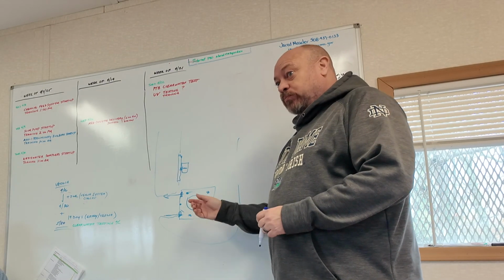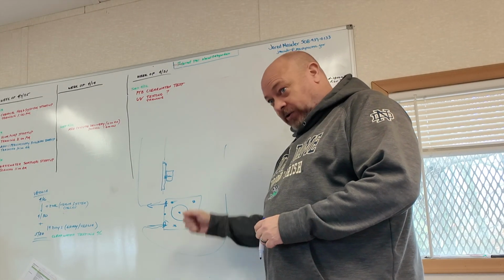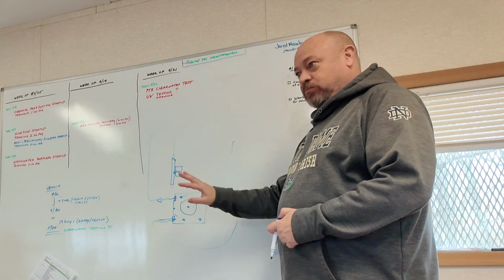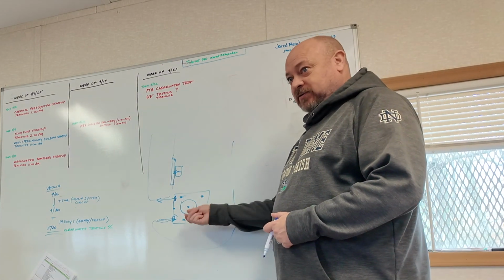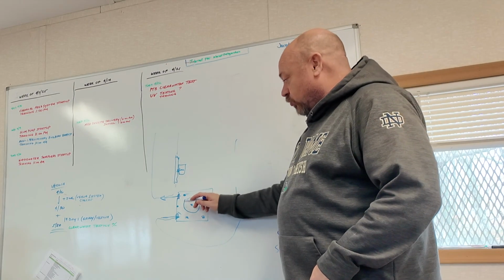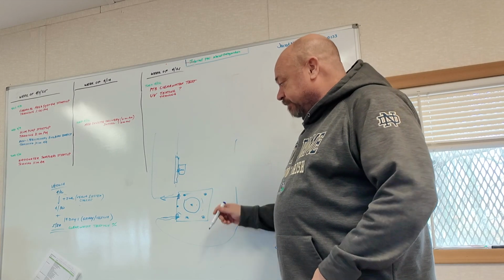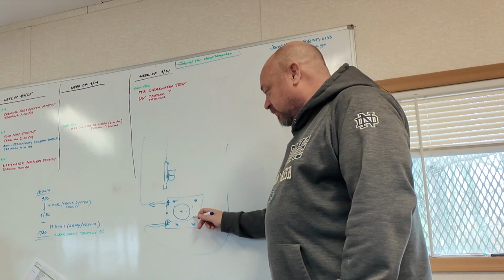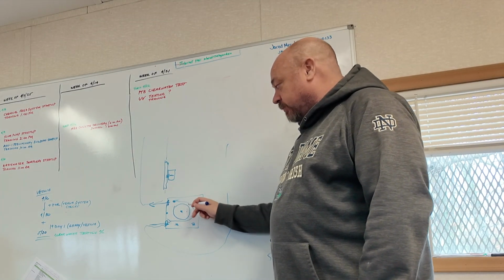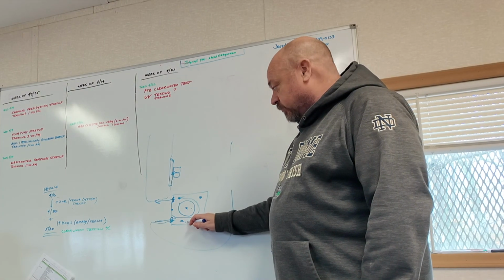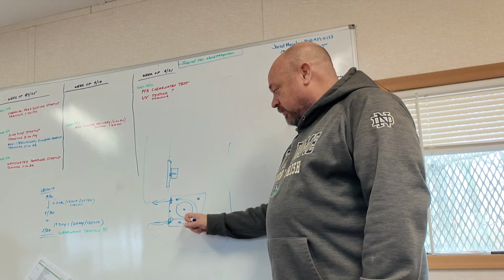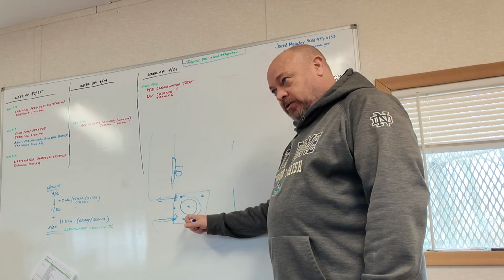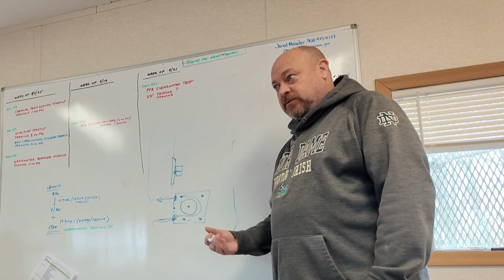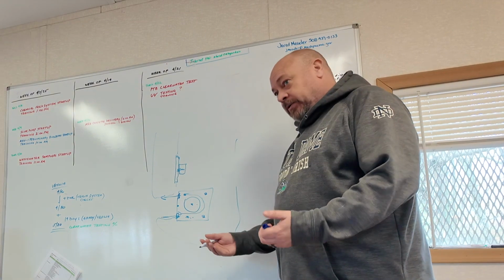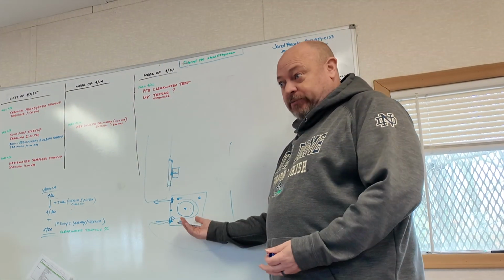I've seen people put channel locks on that, crank it down and just shatter the acrylic cover. Please don't use any tools on this pump, everything's hand tight. Inside here, the roller's rolling, you have your tubing. If this tubing was to rupture, down on the bottom on the inside of the pump is a little conductivity probe. If the product is allowed to go down and bridges the conductivity probe, it'll go into an alarm basically saying, hey, I've gone into a tube failure. Go out there, you obviously isolate the chemical and change the tube.